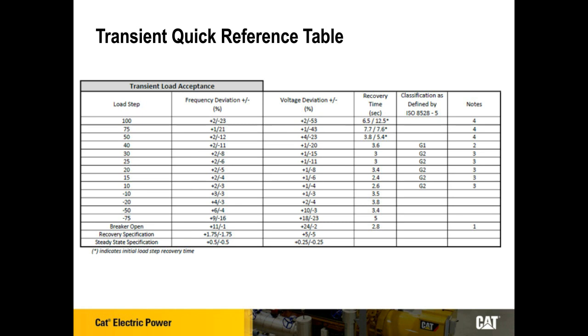The reason hot versus cold is important: if you look at the recovery time column, the third column from the right, for the first three load steps—the largest, at 100, 75 and 50% load—there are two recovery times. The longer recovery time is for an initial cold load step, meaning an engine that has just started and has not run with load. This initial load step will have a longer recovery time than a hot engine. Since we're talking about standby, most of the time the initial load step for a standby engine is on a cold engine, so this is really the recovery time that's important.